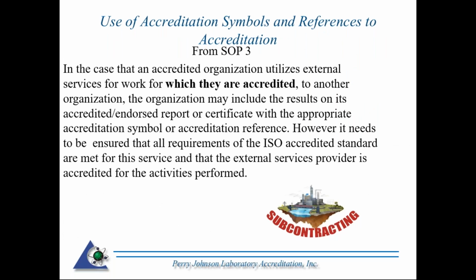All right, subcontracting. Sometimes I go into a facility and I ask if they do subcontracting. And they would say, yes, well, sometimes we will send test weights off to another lab. Well, in that case, what I'm trying to present is they're not accredited to do test weights. They're acting as a middleman, where they have an agreement with the customer. Hey, we'll send all these things in that you can test, and the things that you can't test, you'll send out to another organization that perhaps can test or calibrate it.